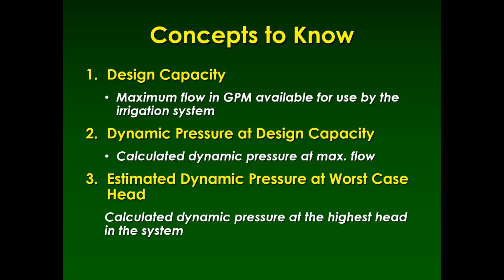So we got to plan out, if we're just, let's say, adding a zone to an existing section, but that last head on that one zone we're adding is another 10 feet up above from where we're connecting it, we're going to have to factor that in, because with kind of going through that dynamic pressure, we have pressure loss as we go up in elevation.